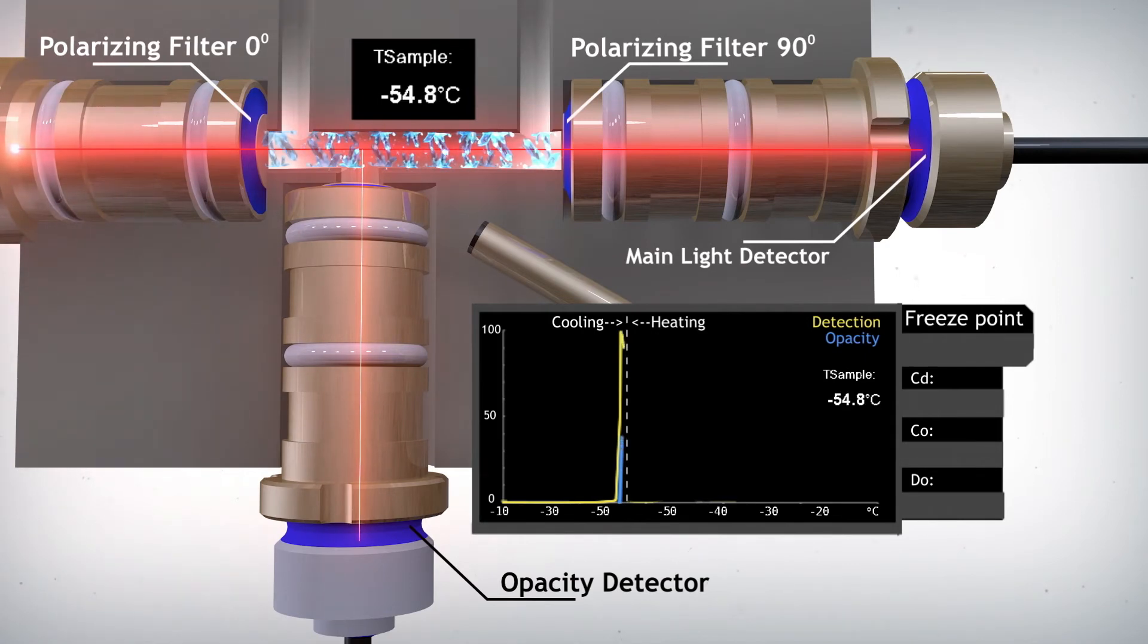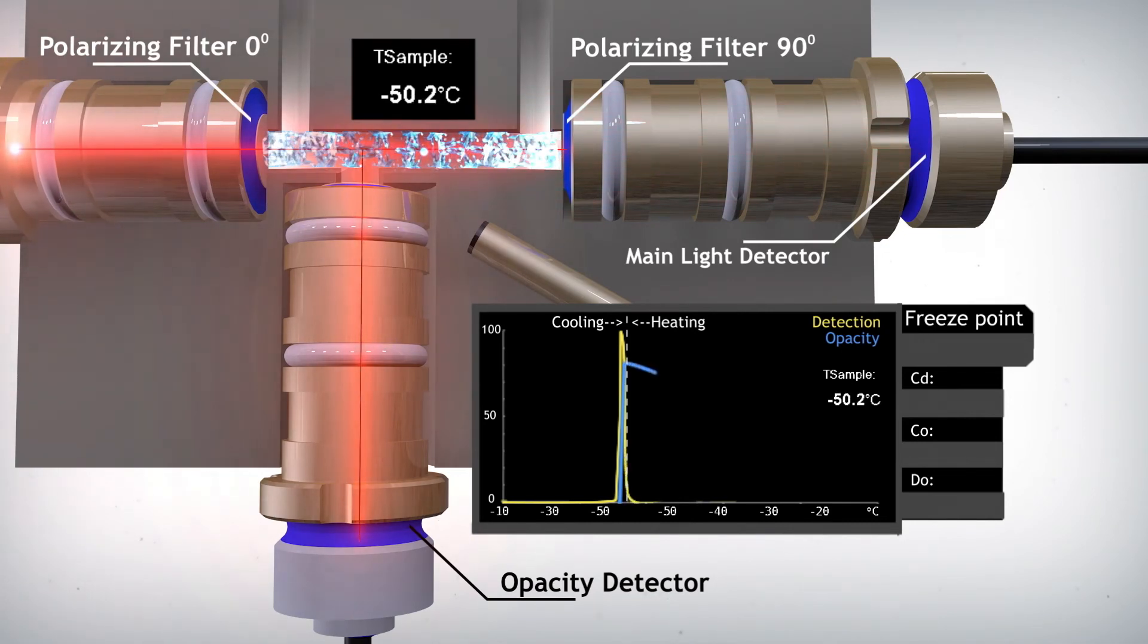When the crystal formation becomes too thick to allow light to penetrate through the sample and the main detector signal stops, OPTI-FZP goes from cooling to heating at 3 degrees per minute, as required per the method. As the hydrocarbon crystals melt away, the light scattered by the remaining crystals allow light back through the second polarization filter, creating a detectable signal again.